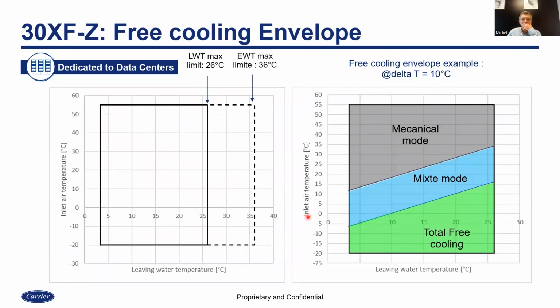It's a kind of function of leaving water or entering water temperature, what the customer will have, and ambient temperature. So you can understand if ambient temperature is low and water is hot, we have much more free cooling opportunity. If leaving water temperature is low and ambient temperature is high, we have mechanical mode. So the question is to know, through the year of operation and through the year loads, how much the unit will operate in total free cooling, mixed mode or mechanical, and you understand that free cooling mode has much higher efficiency than mixed mode or mechanical mode.